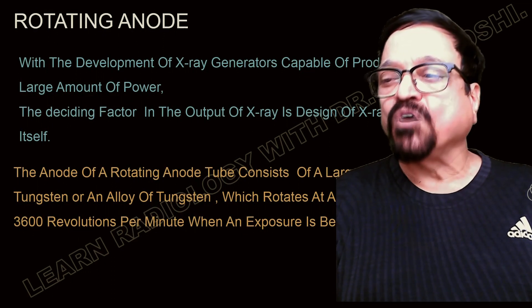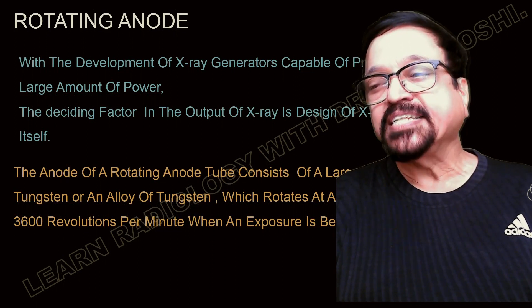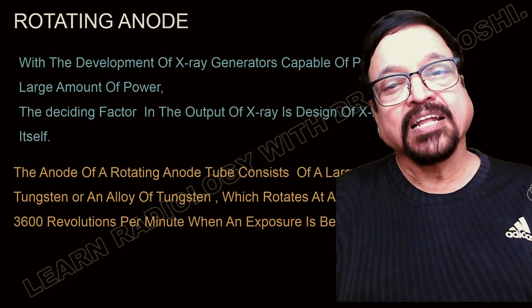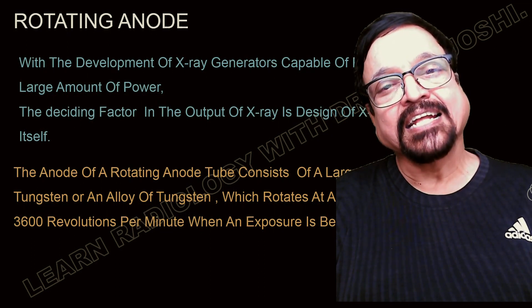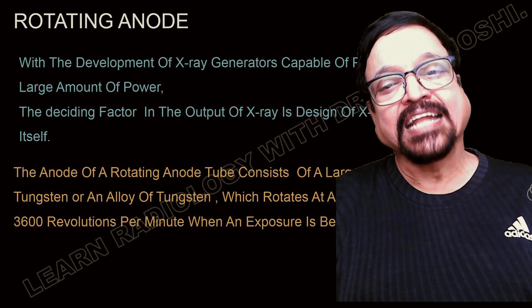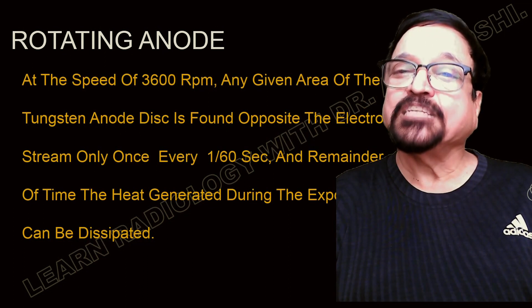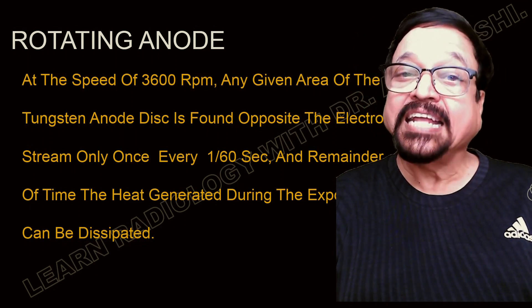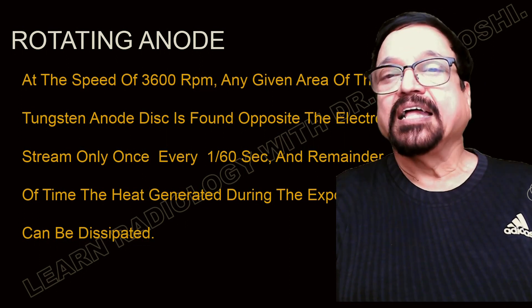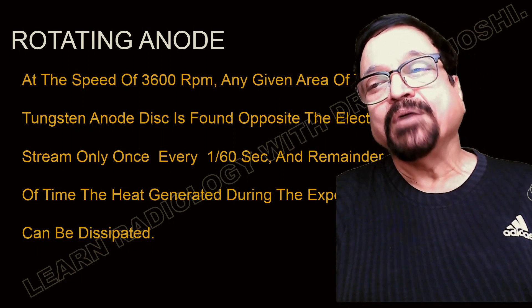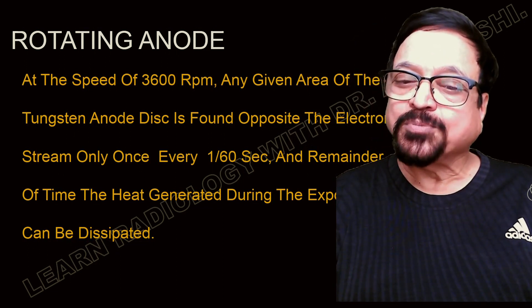The anode of a rotating anode tube consists of a large disc of tungsten or a tungsten alloy, which rotates at a speed of about 3600 revolutions per minute when the exposure is being made. Because the anode is rotating, the electrons being accelerated and hitting the anode will be hitting a different surface each time. Since they are hitting different surfaces, heat dissipation will be faster and large exposures are possible. At 3600 RPM, the electron stream hits a given spot only once every 1/60th of a second, so the remainder of the heat generated during the exposure can be dissipated.